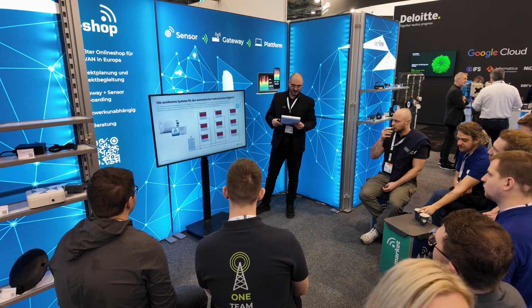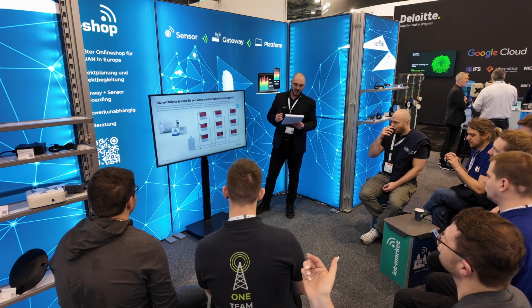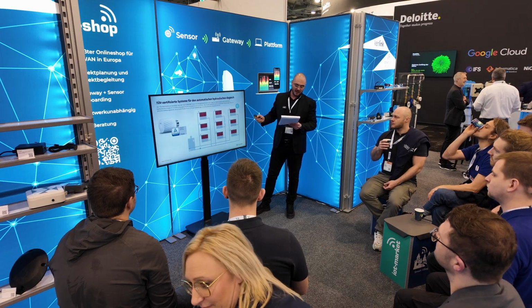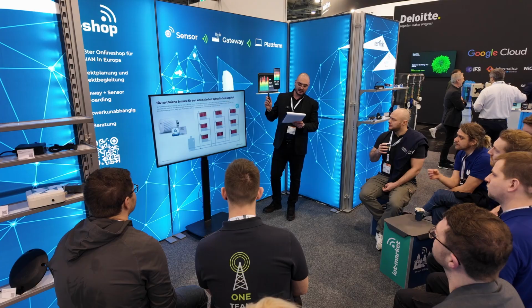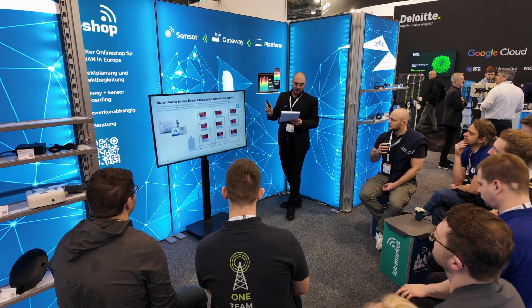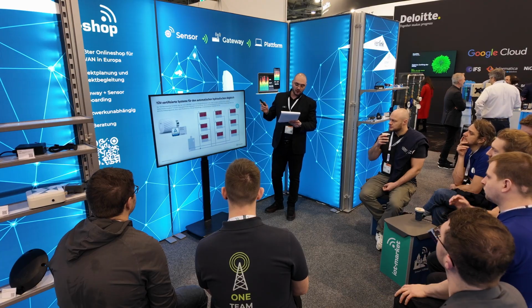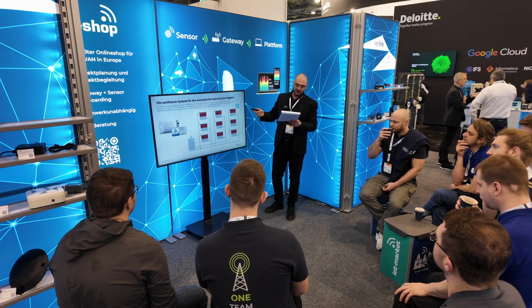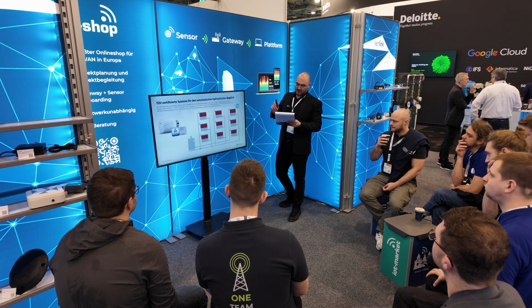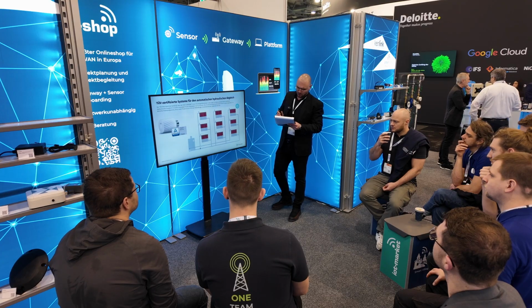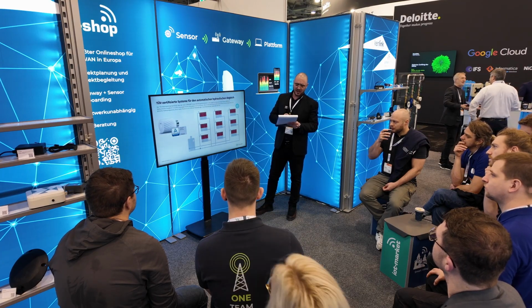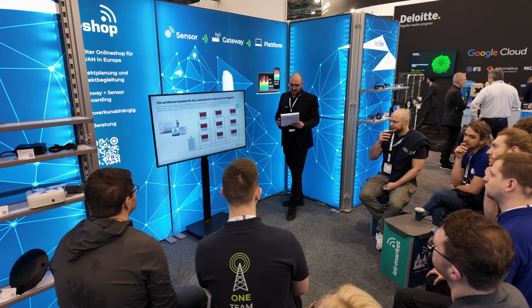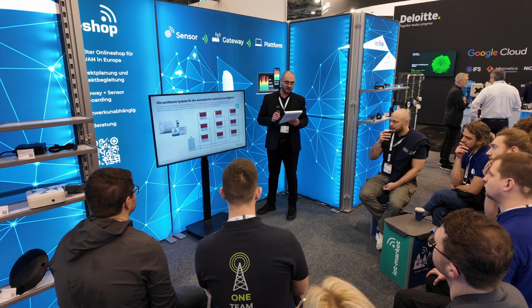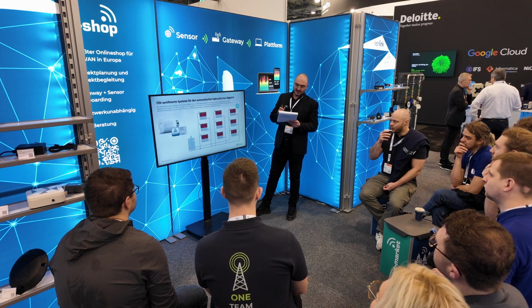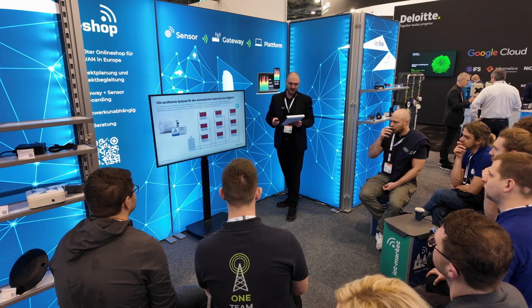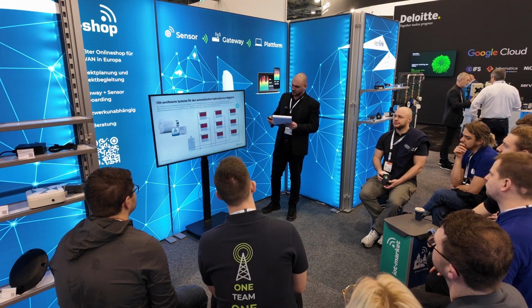Here I want to address a topic that is often underestimated but is very important, especially in Germany, and has a huge impact on energy efficiency: hydraulic balancing. Wiki is TÜV-Rheinland certified for automatic adaptive hydraulic balancing, meaning it can continuously balance an unbalanced system without manual intervention. In practice, this leads to more even heat distribution, fewer overheating zones, and lower system losses, especially in older buildings. This certification is also important because automatic hydraulic balancing is a core requirement in many European funding schemes, such as BEG in Germany. Depending on the project, this can support partial funding, often 15% of the investment, while at the same time improving comfort and reducing energy waste.